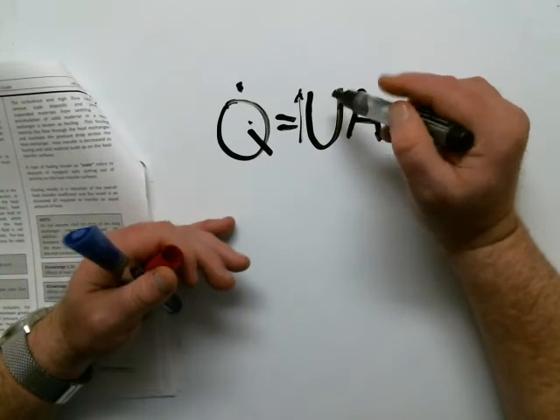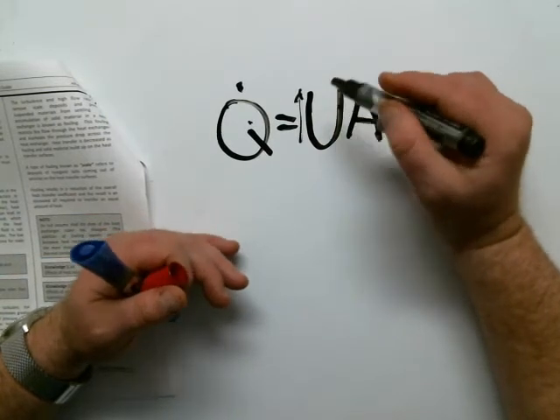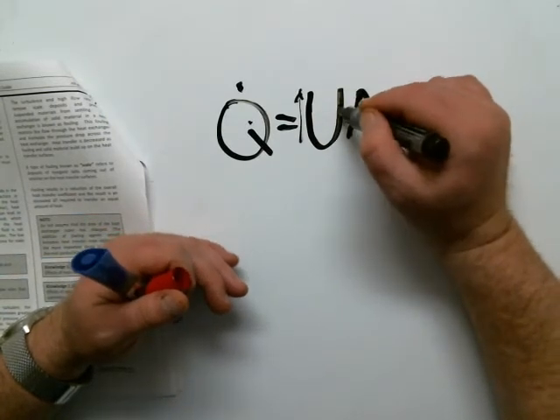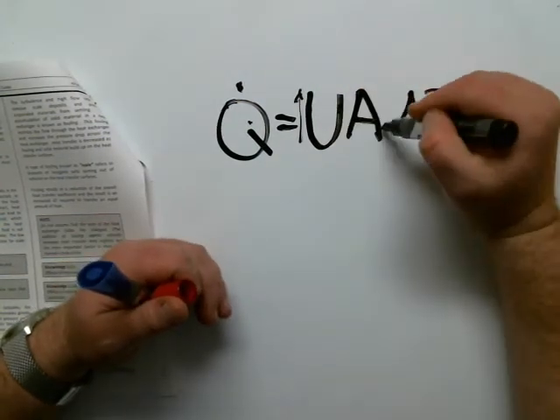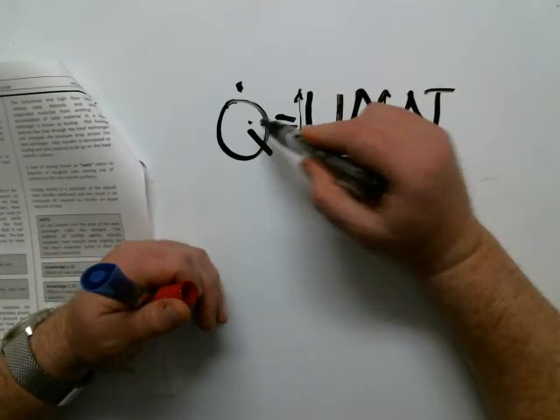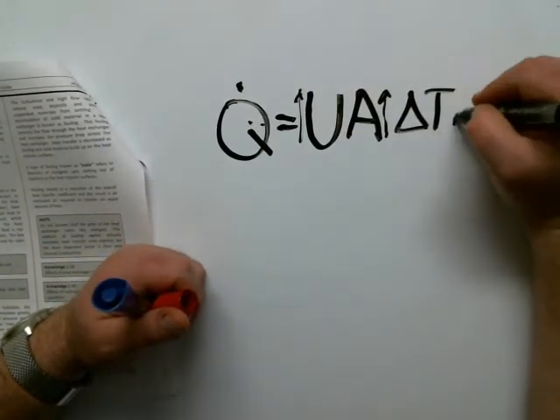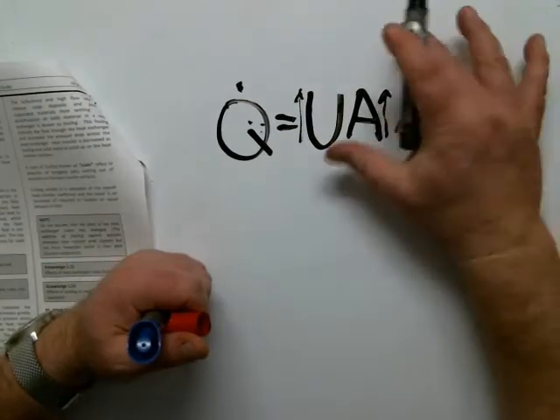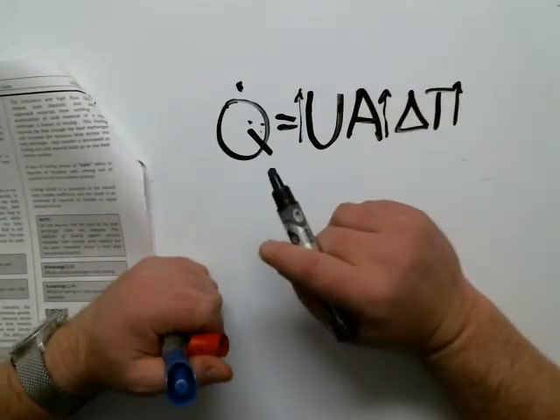Titanium has a higher coefficient than copper. So I would probably, if I could afford it, put titanium tubes in my condenser. And then if I have more surface area, I can transfer more heat. If I have a greater differential temperature between the hot and the cold fluid, I could transfer more heat. Nothing about flow rate in this equation. So some things to look at.